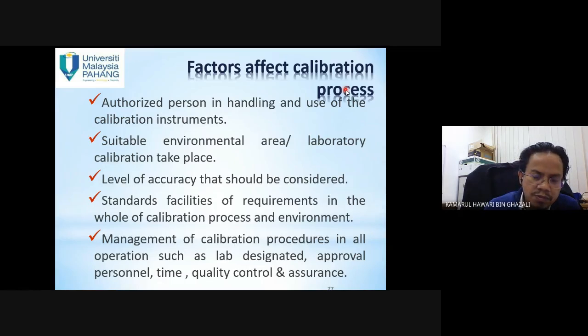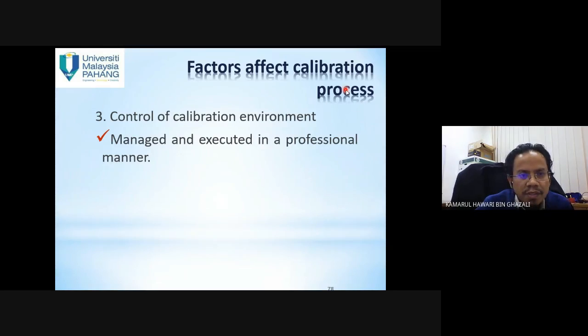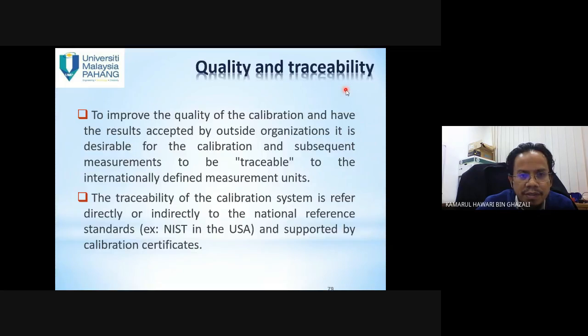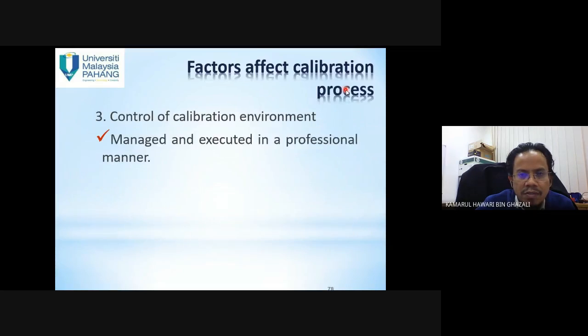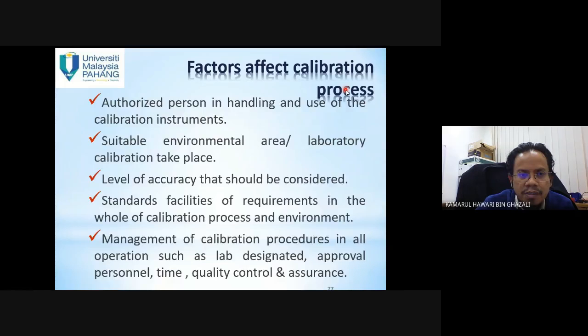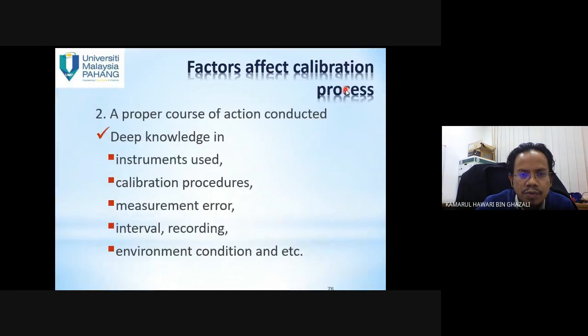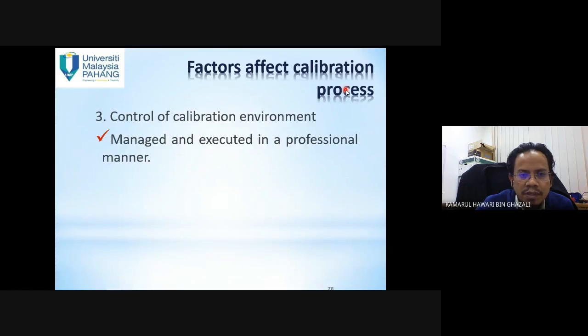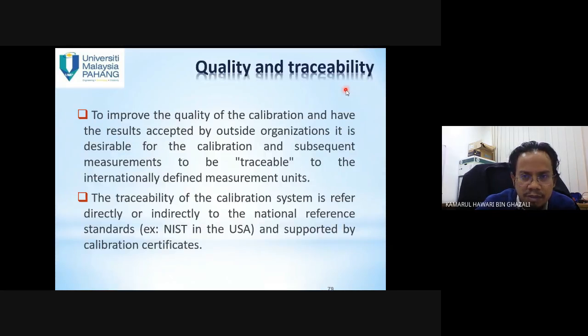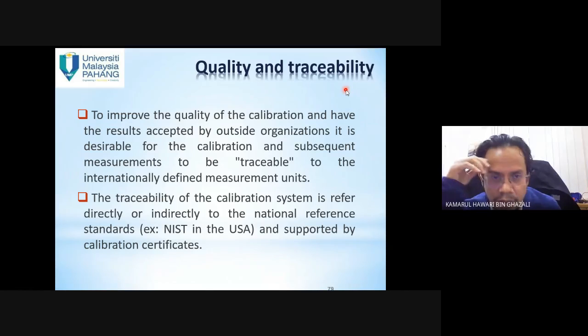Level of accuracy that should be considered. Standards, facilities and requirements in the whole of calibration. Management of calibration procedures in all operations. Third, control of calibration environment, managed and executed in a professional manner. So those are all the factors that affect calibration. There are three factors: one, instrument used for calibration; two, proper course of action; and the last one, control of calibration environment. Quality and traceability, to improve the quality of the calibration and the results accepted by outside organizations.